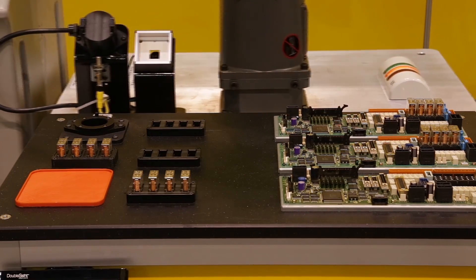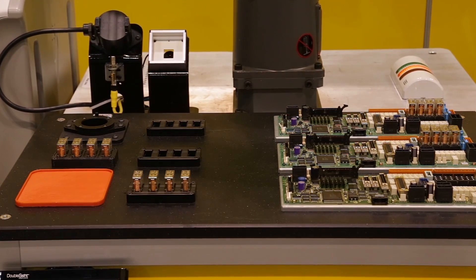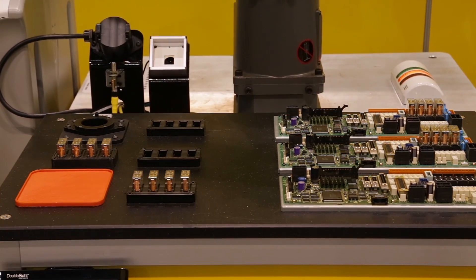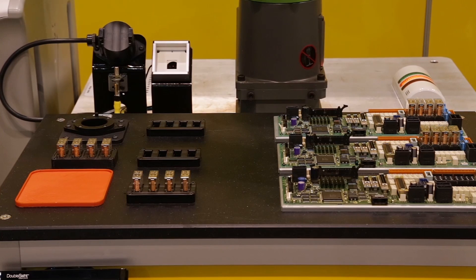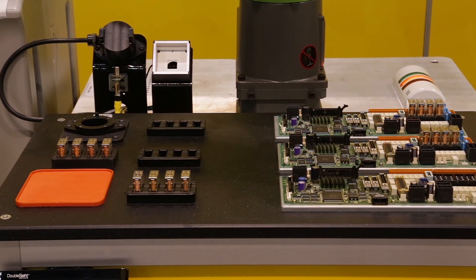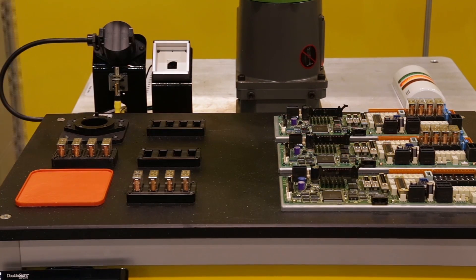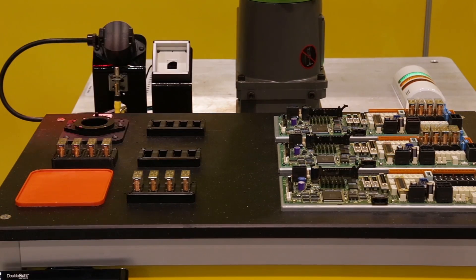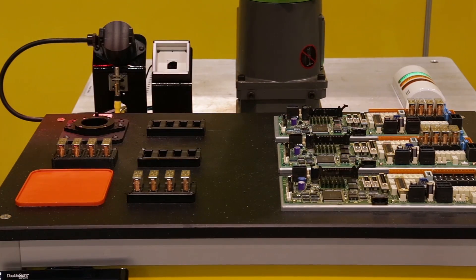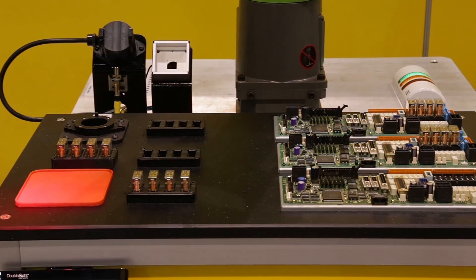A stack light located on the robot's platform turns yellow when the robot is in transportation. It turns green once contact stop is armed on the robot, and the red light only appears during robot fault.